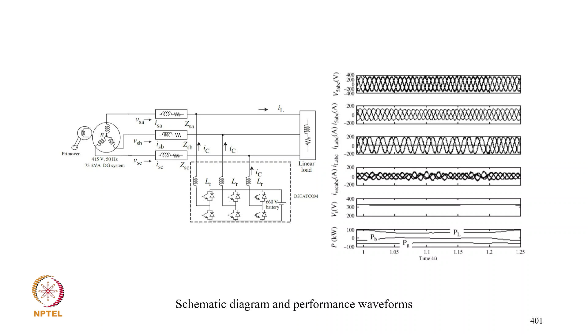Coming to the solution, given that the DSTATCOM with a 660 volt battery at the DC side of the VSC is connected to an isolated 3-phase 3-wire 415 volt 75 kVA DG engine generating set, the rating of the battery calculated for 4 hours backup is E equal to percentage of load times PS, that comes to 75 kilowatt hour. Since the battery is required to feed 25% of load active power, the battery current is IB equal to E upon VB into S, so it comes to 28.41 ampere.